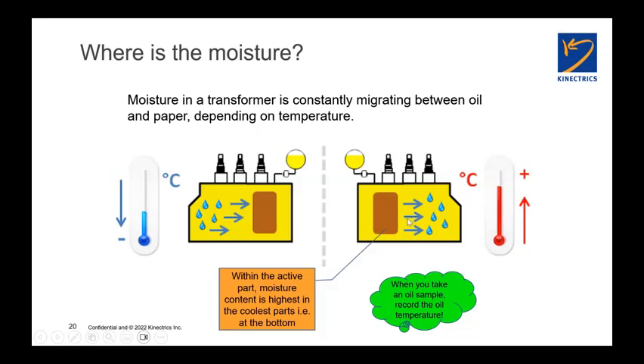Okay. We also know heat rises in everything, and in a transformer, the same is true. The top part of the core coil assembly is always hotter than the bottom, which means by this process, the bottom part of the core coil assembly is always going to be wetter, have more moisture than the top part. And so this partitioning is why it is so critical that when you take an oil sample to do tests at a laboratory, you must record the temperature of the oil sample that was taken, because that's the only way that we can look into this partitioning.